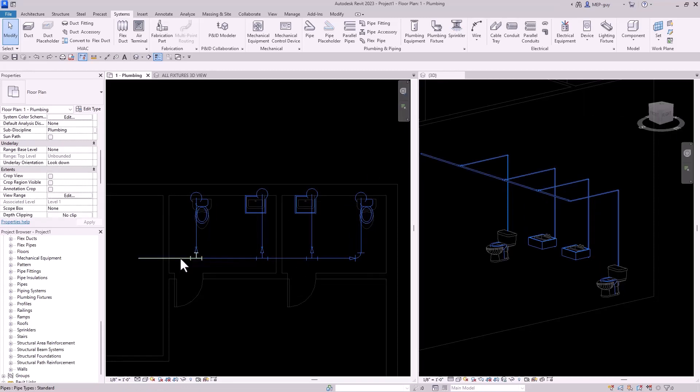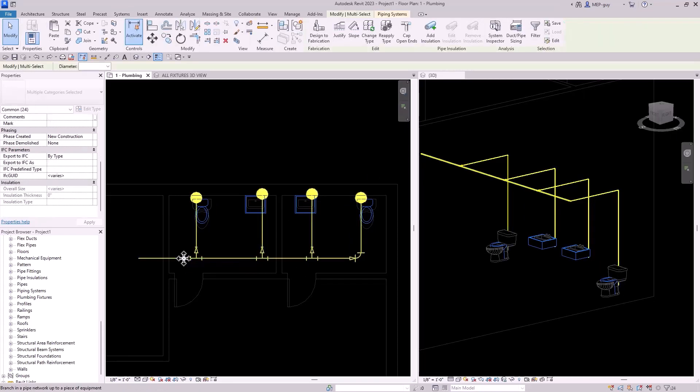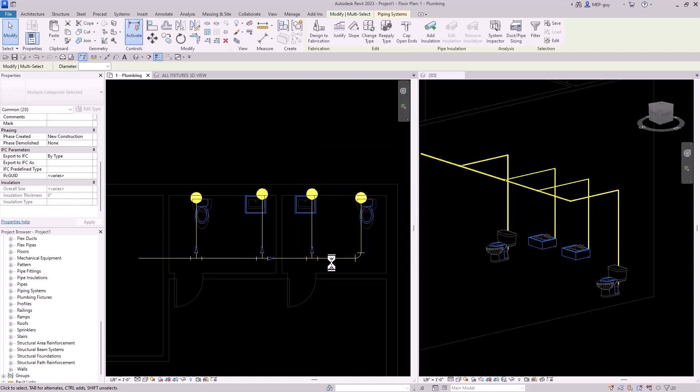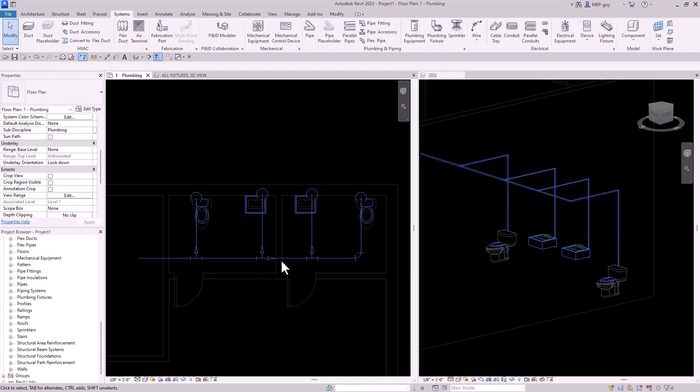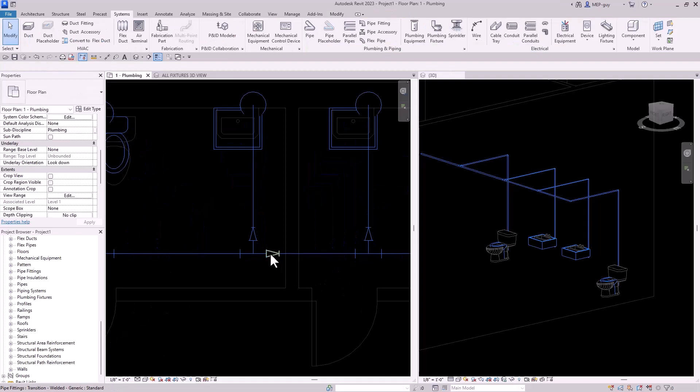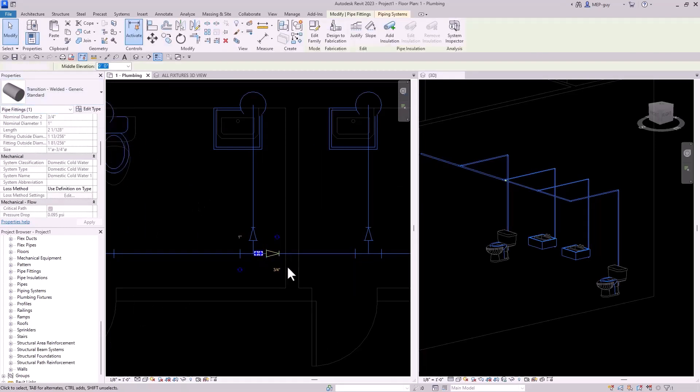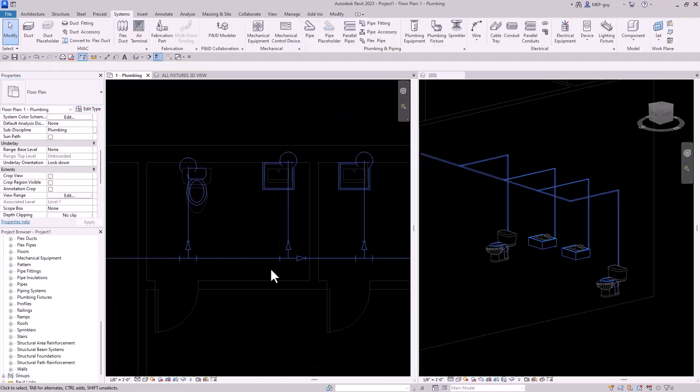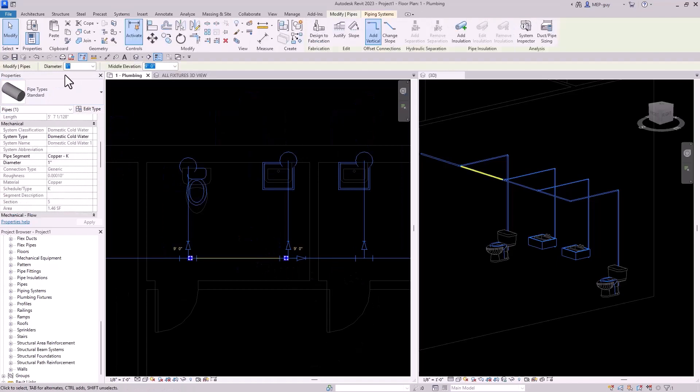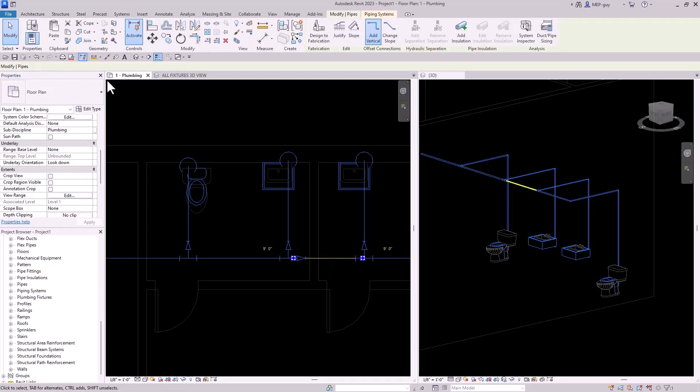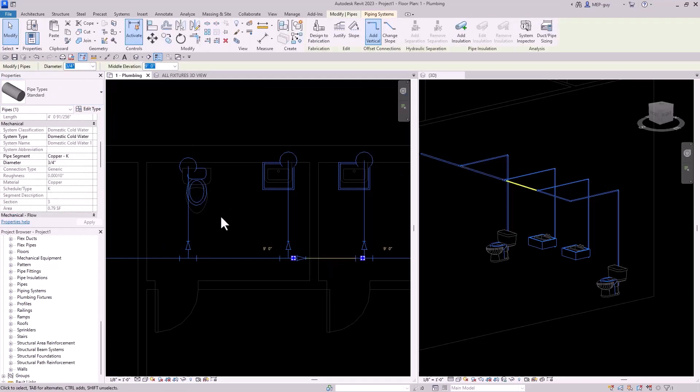Now I promised you guys I would size this piping for you. So all I have to do is I have to tab into all of my pipe. We'll go up here to the duct pipe sizing tool, set our velocity to eight feet per second. I'll use calculated size only and click OK.